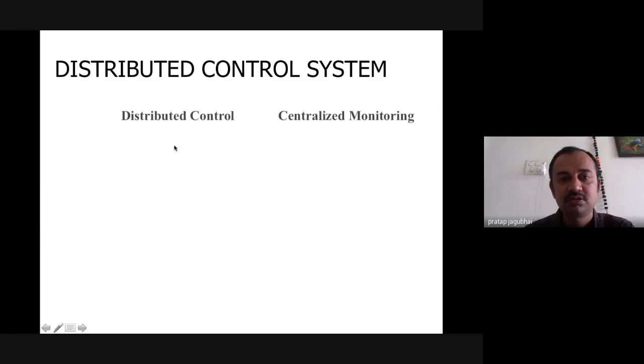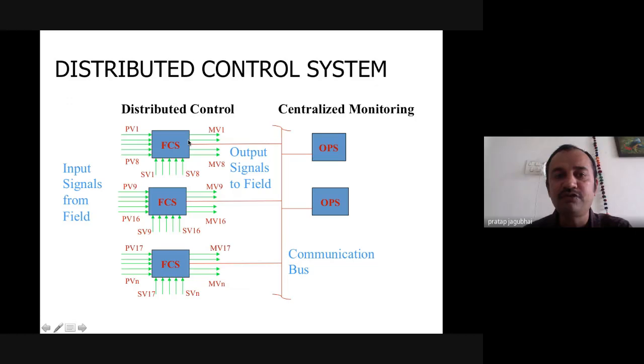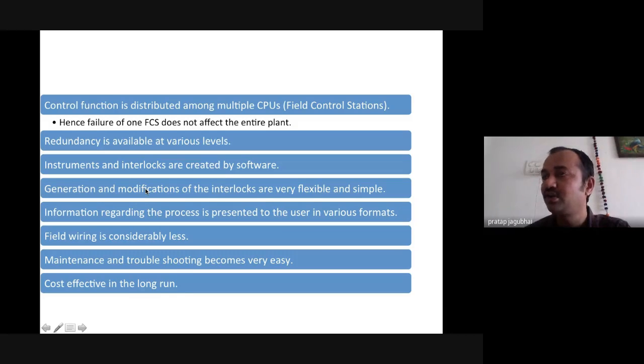Now, if I go into the construction point of view for the DCS side, DCS takes the individual field control systems, talking to the output signals in the form of Modbus communication over a single common bus bar, which is communicated to the operating stations where your SCADA is installed inside the computer. These operating stations are computers having a better representation of the controls of the boiler process, where you can easily modify your set point, configure it, and control the parameter. The advantage of the DCS is that even if a local controller fails, the complete boiler house control is not disturbed. You can take corrective action, replace and troubleshoot that controller, but the rest of the controls remain operational.